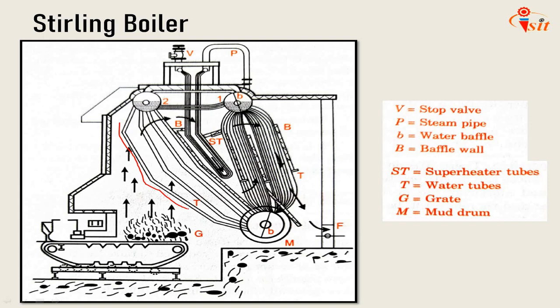The figure shows a small sized Stirling water tube boiler. It consists of two upper drums, drum one and drum two, which serve as steam drums, and a lower drum known as the mud or water drum. The steam drums are connected to the mud drum by banks of bent tubes. The steam and water space of the steam drums are interconnected with each other so that balance of water and steam may be obtained. A manhole is provided at one end of each drum for cleaning operations.